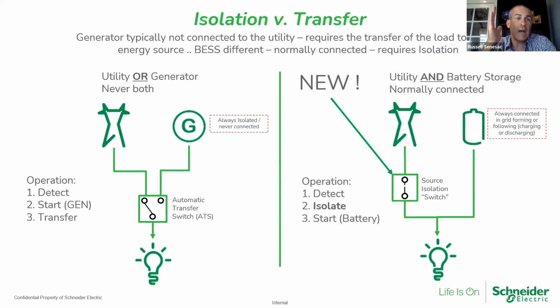So normally connected, power goes out, now I open the switch. When that switch is open, the battery and the inverter know they're isolated, so now they can create power for the building, with that switch remaining open until the power comes back. When the power comes back, the inverter and battery know from the switch, which says stop making power, and now I'm going to reconnect you back to the grid. So it stops making power, I reconnect it back to the grid, and now I'm back to a normal grid-following connected scenario.